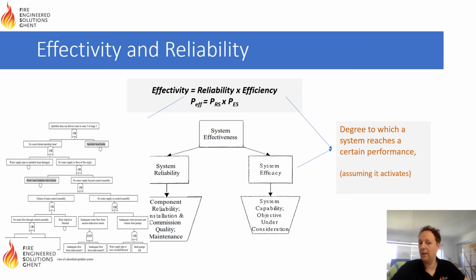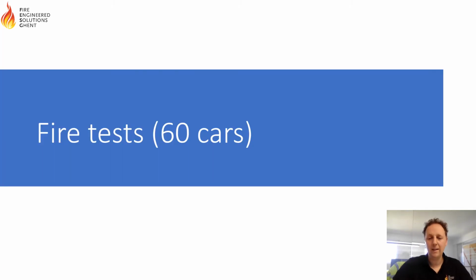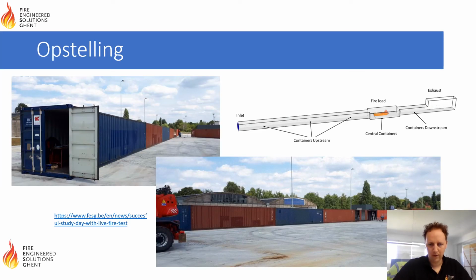Now, in order to say anything useful about the efficiency or system efficacy of a sprinkler system, we need to perform fire tests. So this leads to the test campaign where we performed 60 fire tests. We basically built a 70-meter long representation of a car park out of containers. As you can see here, we had 3 containers where we could put 3 cars, so the burning car and 2 adjacent cars, to look at the fire spread. This zone was also equipped with sprinklers. Then we had containers on the upstream to look at the smoke spread upstream and then downstream. And here we could position a fan.